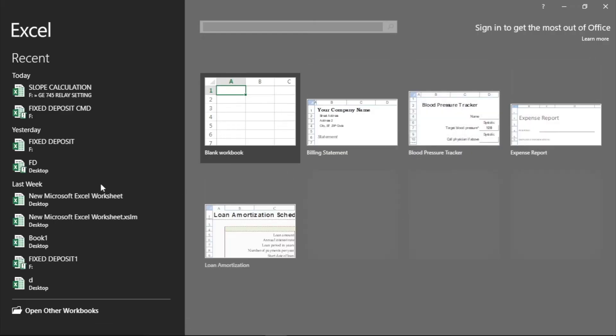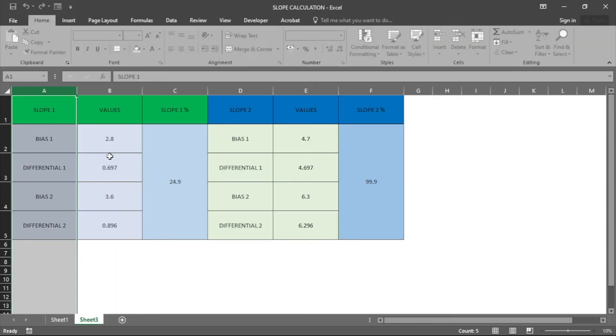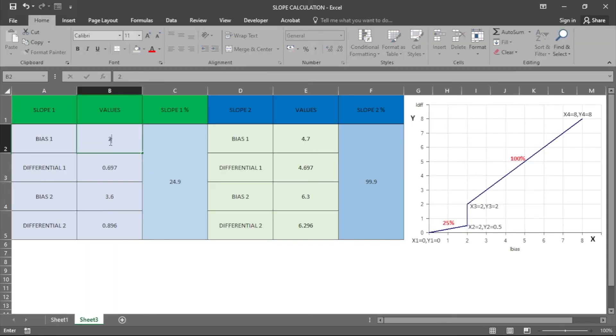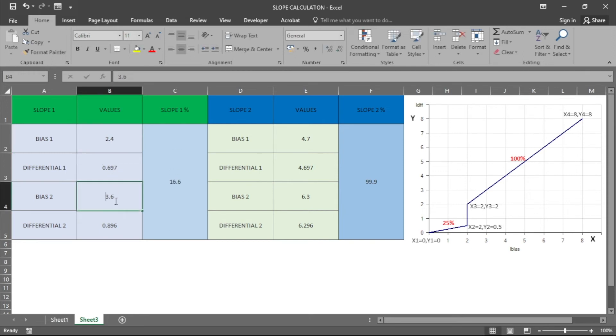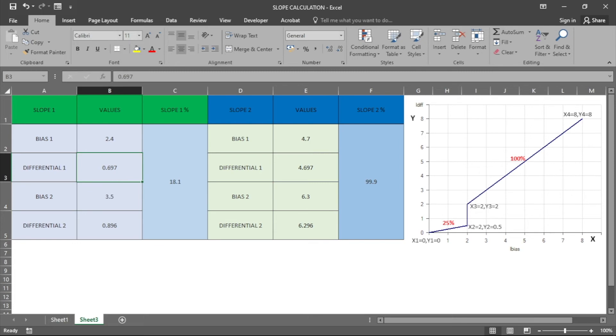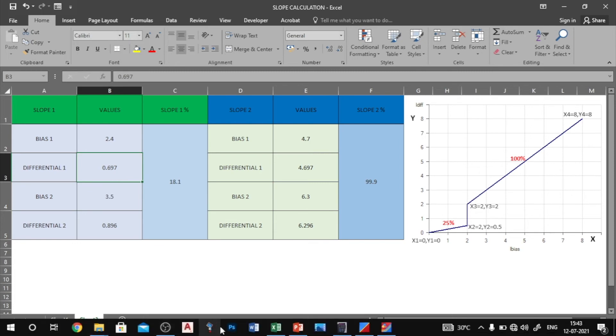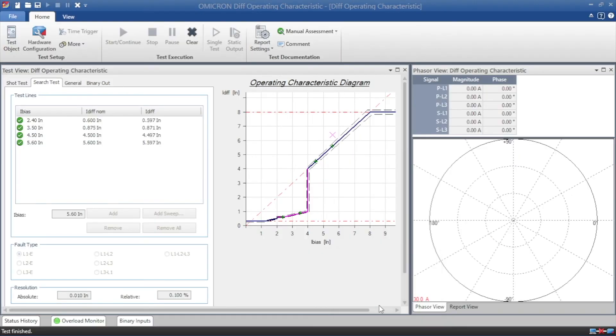Here we will give the exact tripping characteristics percentage. Here the Excel file already created slope calculations. You see I enter the value for the bias 1 and bias 2, for the slope 1 and differential value I have to enter now.